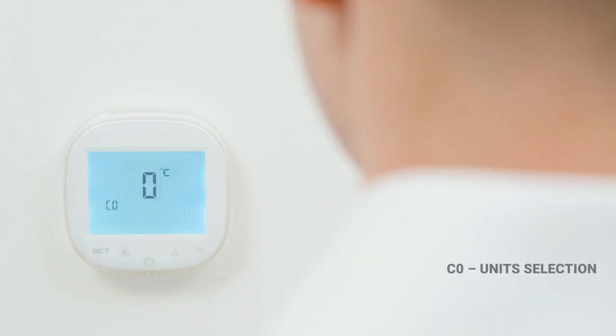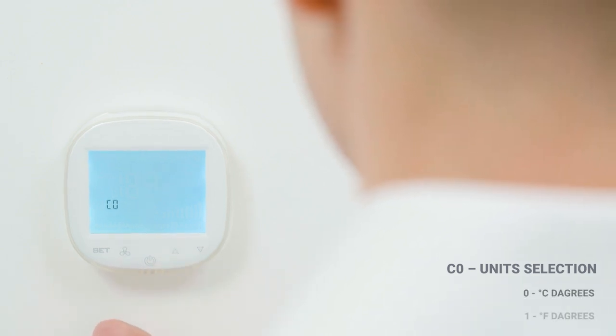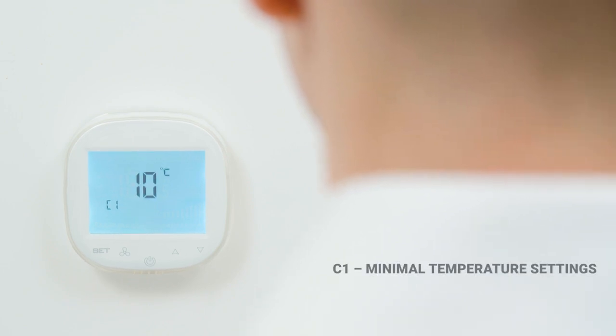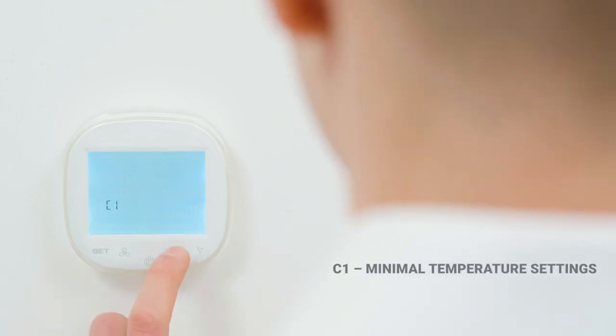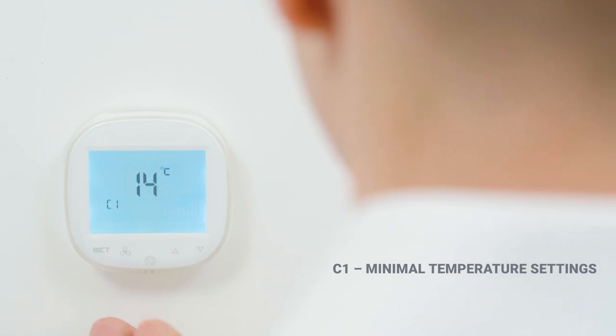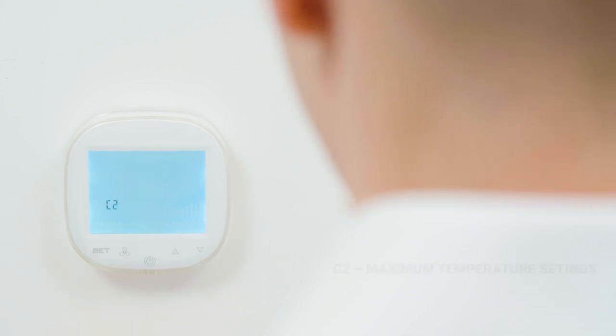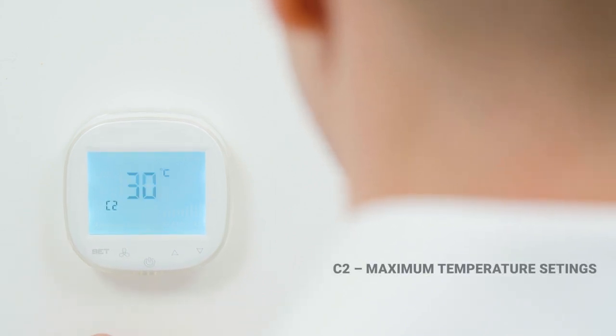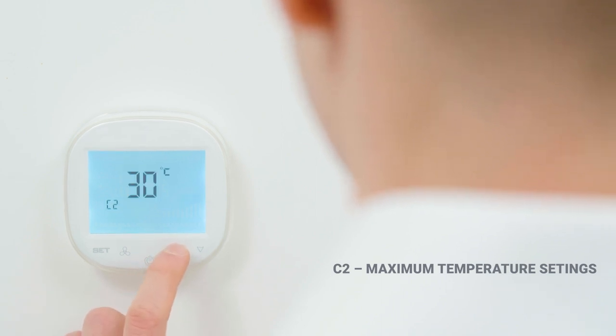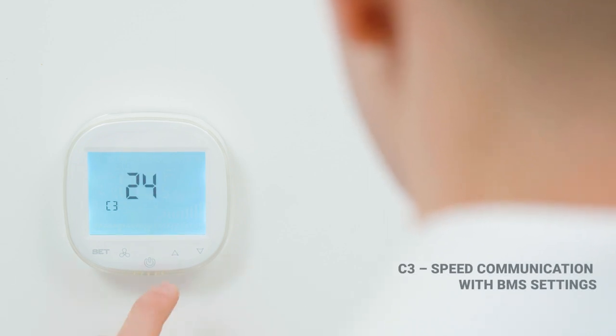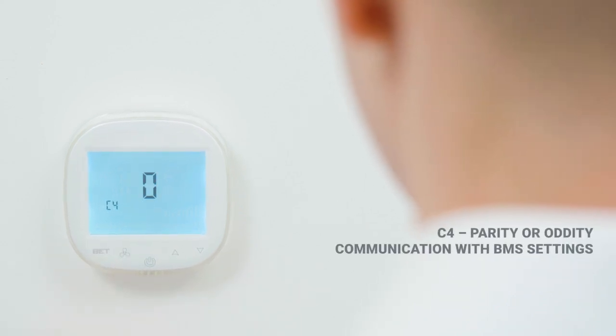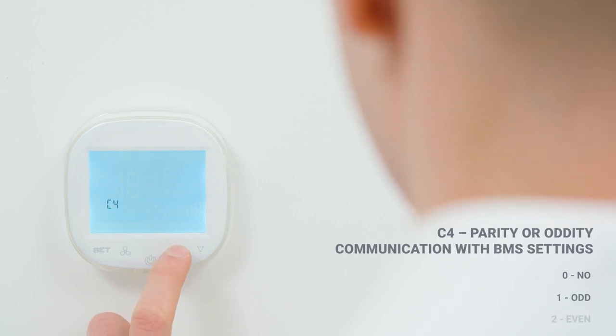Function C0, selection of units. We can choose between Celsius degrees and Fahrenheit degrees. Function C1, set minimum temperature. We can set a value from 5 to 15 Celsius degrees. Function C2, set maximum temperature. We can set a value from 15 to 40 Celsius degrees. Function C3, speed setting for the controller to work with the BMS system. Function C4. It is even parity and odd parity setting for cooperation of the controller with the BMS system.